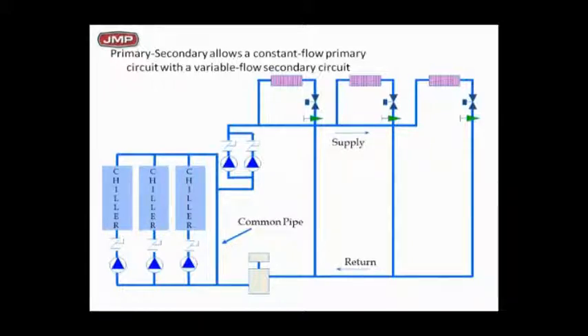Here's a typical one with primary-secondary chiller loop. I have three chillers, three pumps, common pipe, secondary loop with variable flow. I got constant flow on the chillers, variable flow on the secondaries.